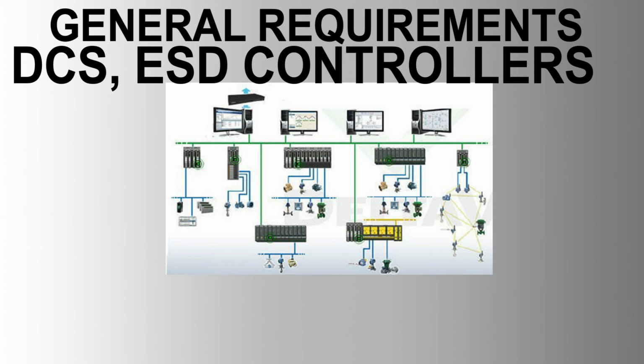General requirements for emergency shutdown ESD controllers. 1. Types of I/O cards. Analog input AI cards. Designed to accept 4 to 20 mA DC signals with a maximum input resistance of 250 ohms. Capable of 1 to 5 VDC input option with input resistance equal to 500 k ohms or greater. Input faults such as open circuit and short circuit are detected by the I/O module.